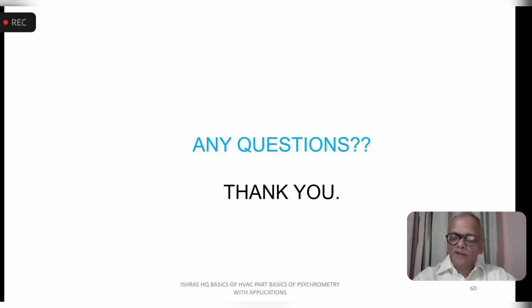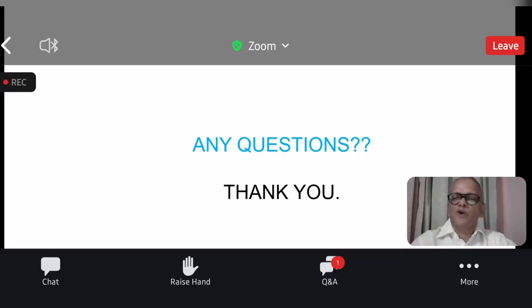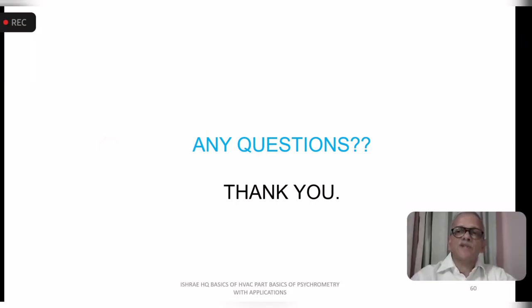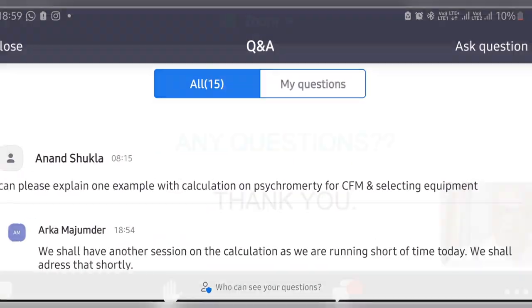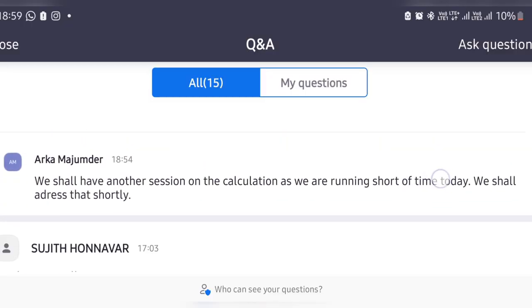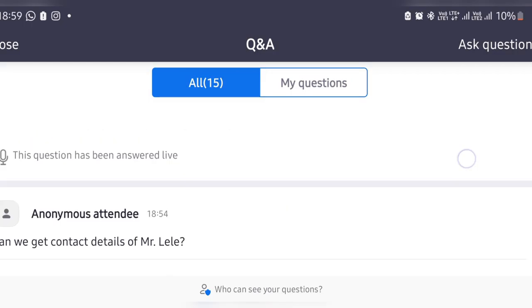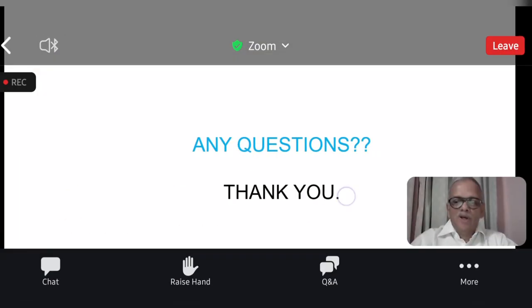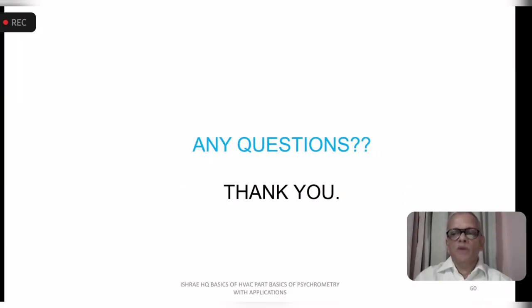And there is a tendency of lowering the temperature of the chilled water from 45 to 42, but it taxes the refrigeration system. It becomes more expensive. And the tendency will be that just for one space, I'm not going to change the entire design. But if you have identified such spaces, you have to give them due respect and give an independent system.